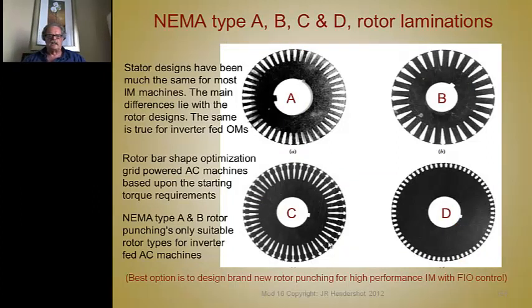Now let's talk about the laminations that have been designed for induction motor rotors used with grid power with constant voltage and frequency. They've classified these into four classes: NEMA type A, B, C, and D. And rotor designs for the last 100 years have been one of these four types, and each one, as you'll notice there, has different shaped slots and/or rotor bars. Most of these are die cast, but not all of them.